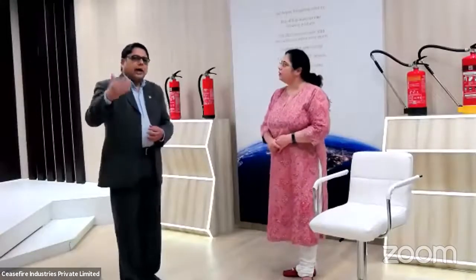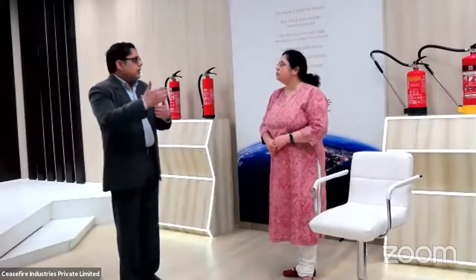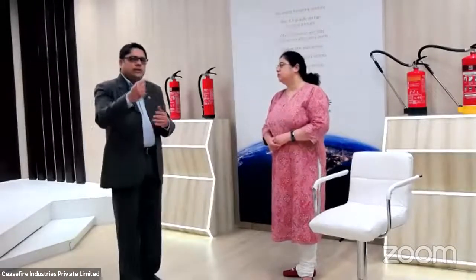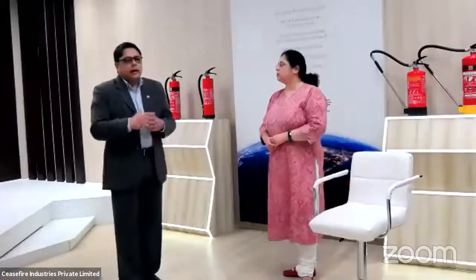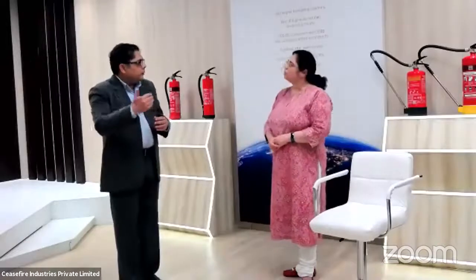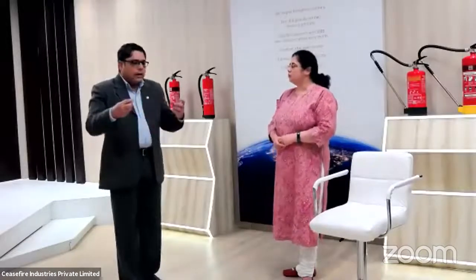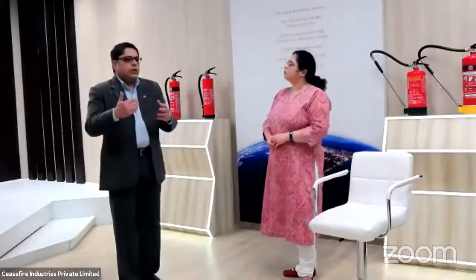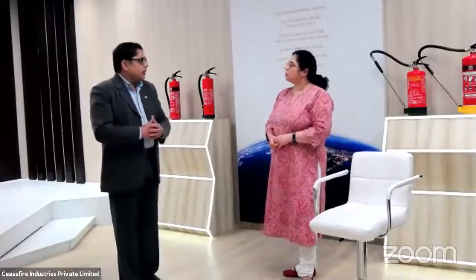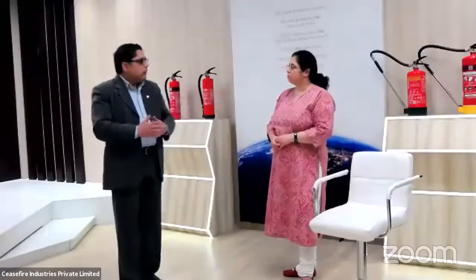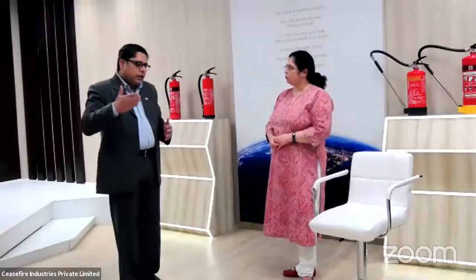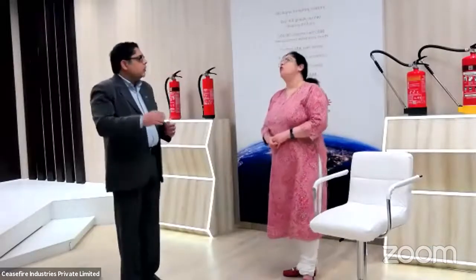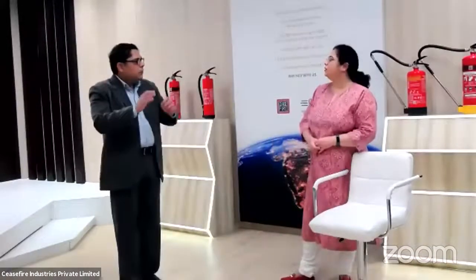As I told you in the video, we have various kinds of extension ranging from 0, that is just the bulb inside, and then 100 mm and 150 mm parallel extensions, with the 0 to 150 mm able to go up to 200 mm. So depending on what is your width, you can have your detector within the enclosure to have optimum detection and extinguishment.